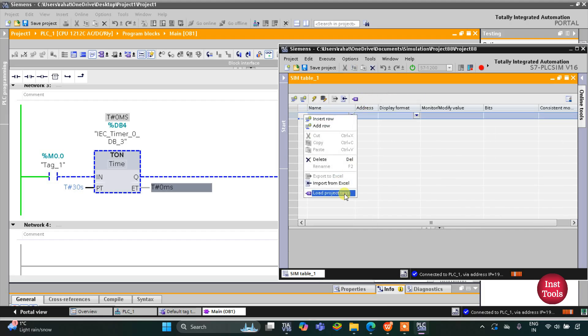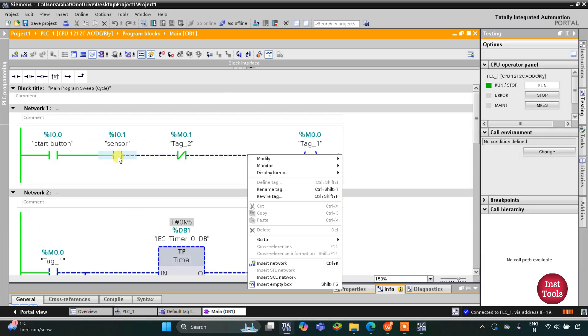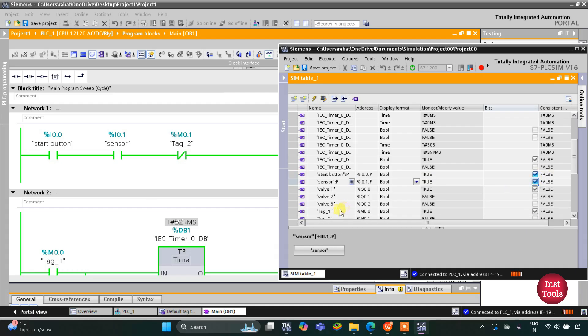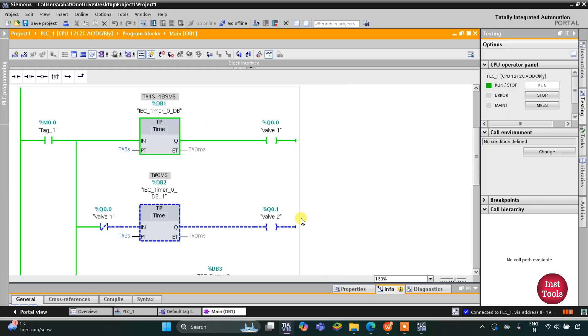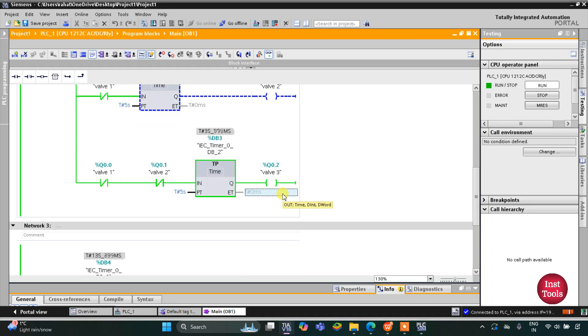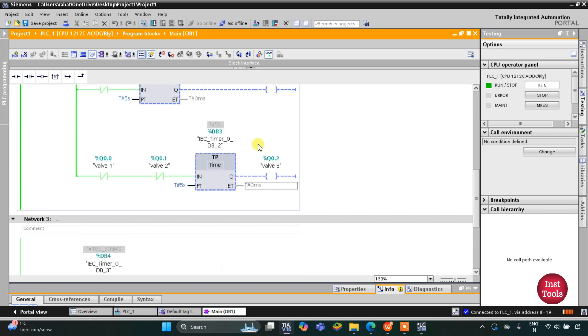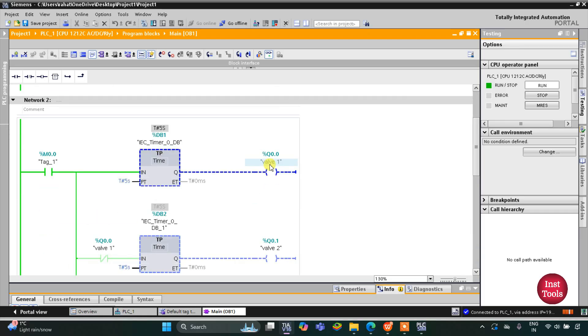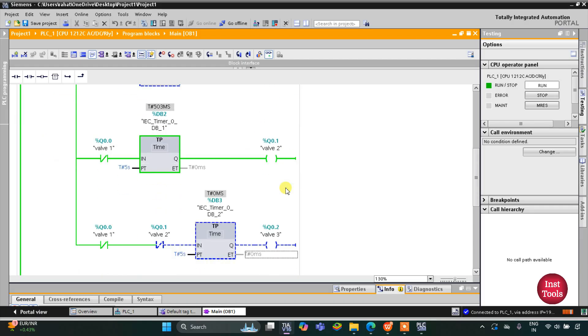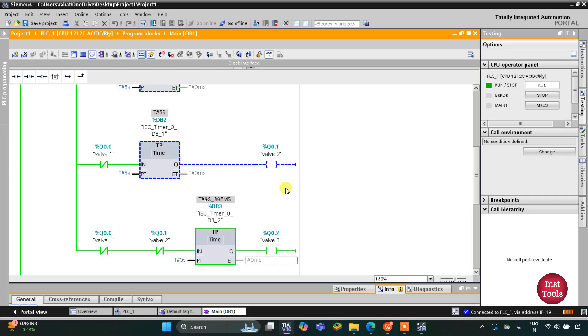Go to Simulation Tables and Simulation Table 1. I right-click and click Load Project Tag. When I turn on the start button nothing happens because the sensor also needs to detect movement of fishes. When the sensor is activated, M0.0 turns on, Valve 1 (Q0.0) turns on, then Valve 2 opens for five seconds, then Valve 3 opens for five seconds. It then waits 15 seconds, M0.1 turns on and off, M0.0 resets and turns on again, and Valve 1 turns on again. Valve 1, then Valve 2, then Valve 3 cycle repeatedly.